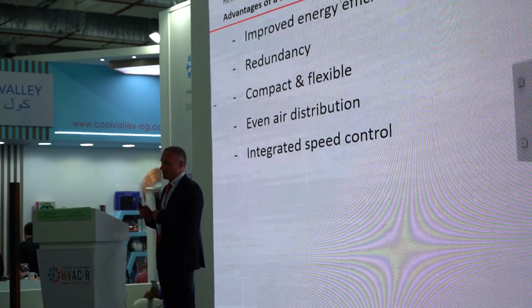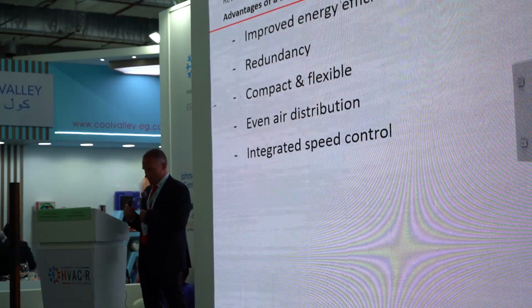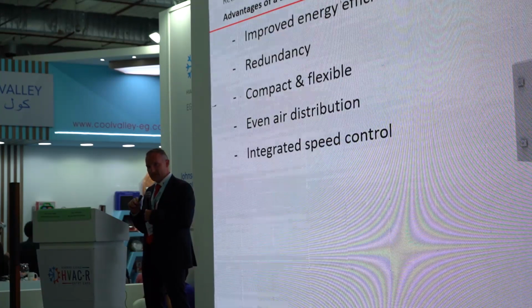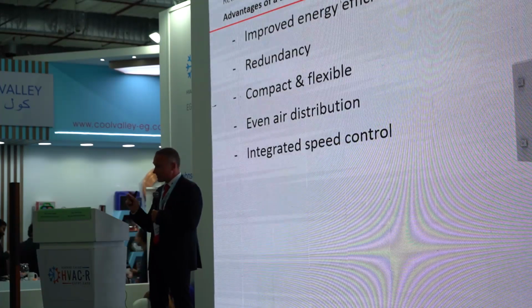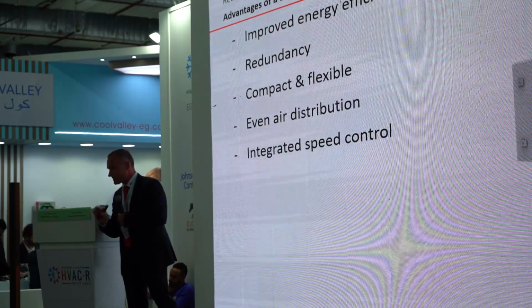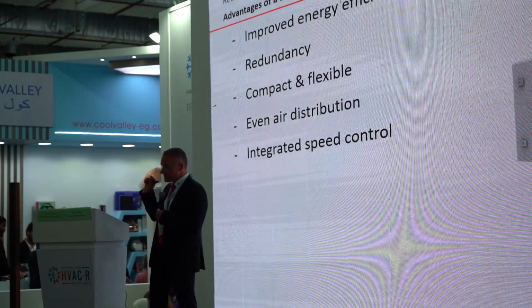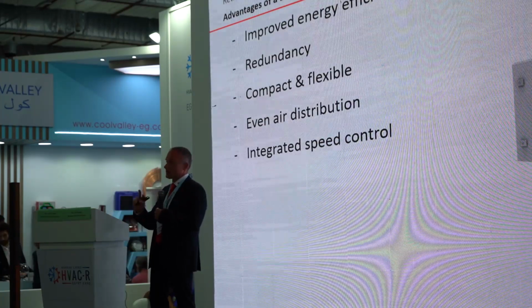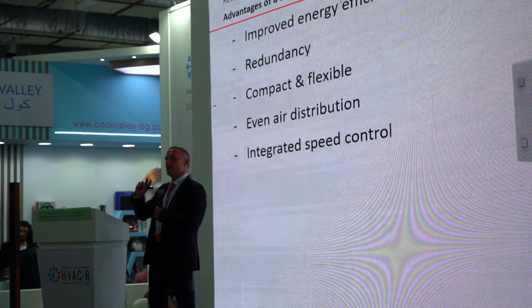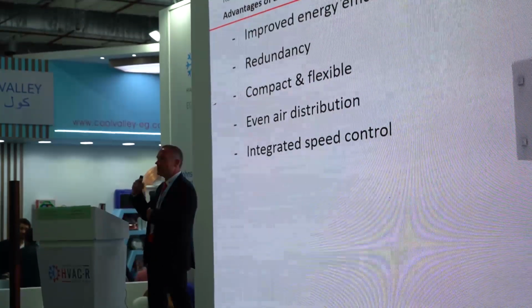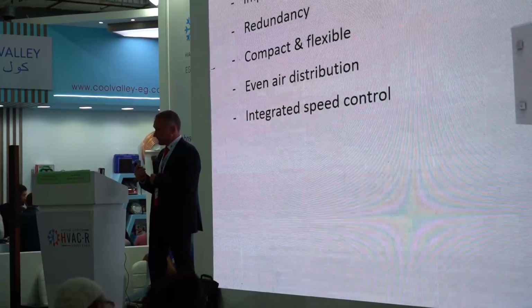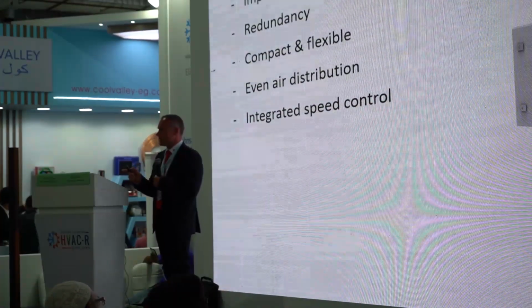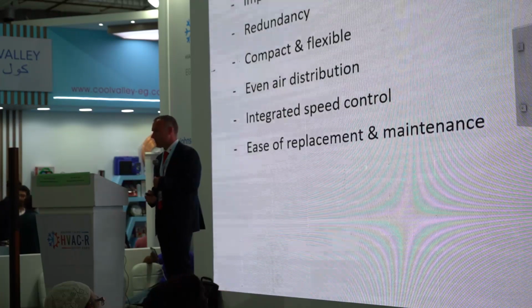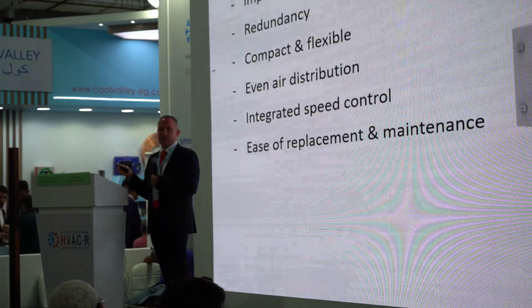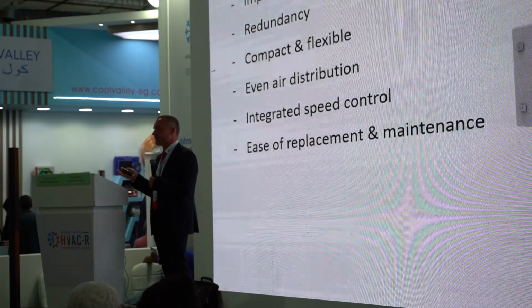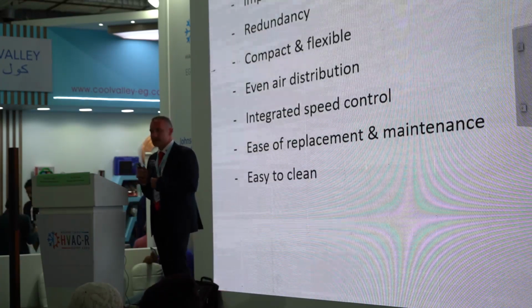The EC motors have an internal electronic. Normally they are controlled with a 0 to 10 volt signal, and this electronic works like a frequency converter, but it's integrated in the motor. The signal goes without any losses inside the motor, and the electronic generates the right magnetic field and the runs per minute in the direction of the magnetic field. Later on there will be an explanation of how an EC motor works. Due to the weight, we have ease of replacement and maintenance, and it's easy to clean.